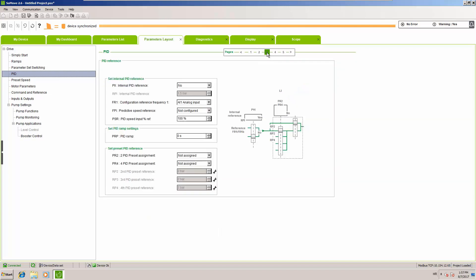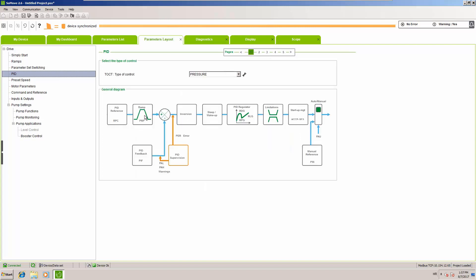On step three, we handle the reference. We will handle our reference with analog input 1, set up with a potentiometer connected to that analog input. Additionally we will set up a PID ramp time so we can ramp up and down when changing the reference — this is one of the things that can also influence oscillation during the transition phase in your system.